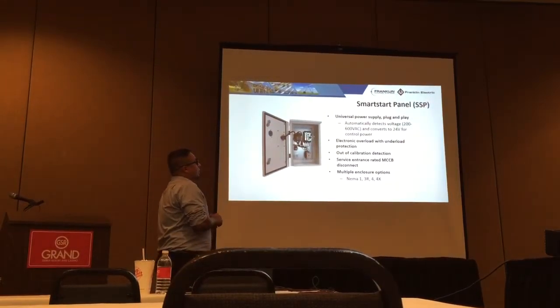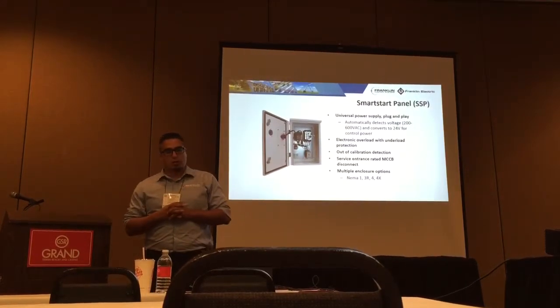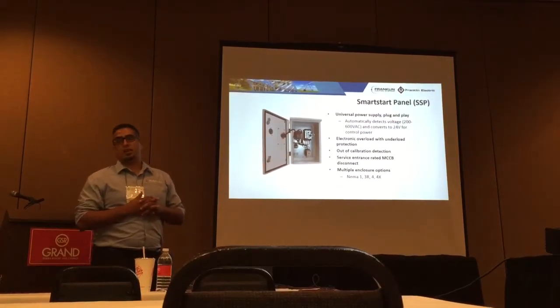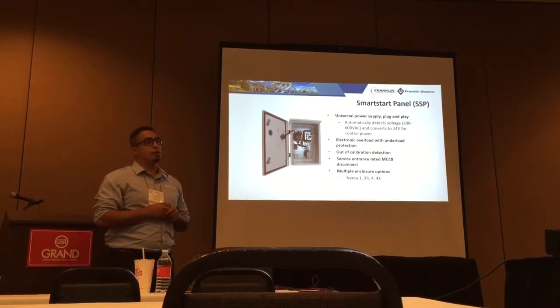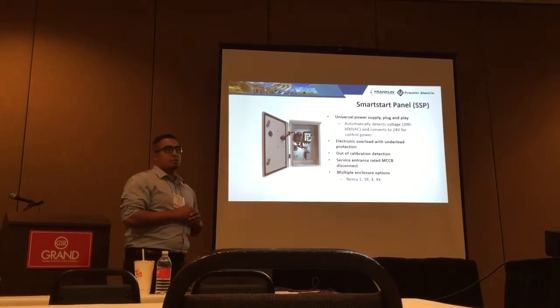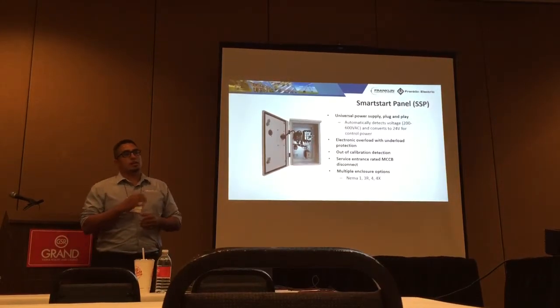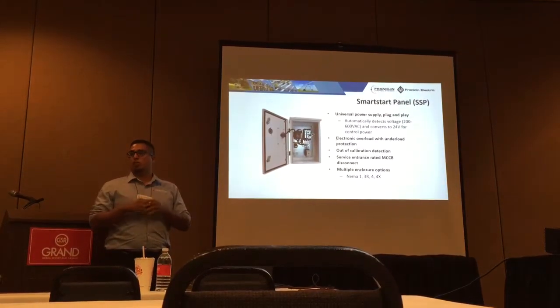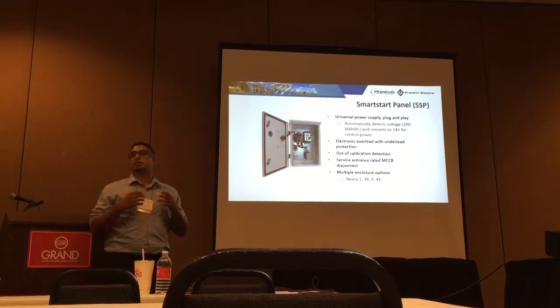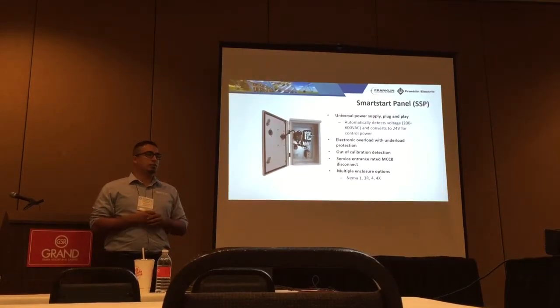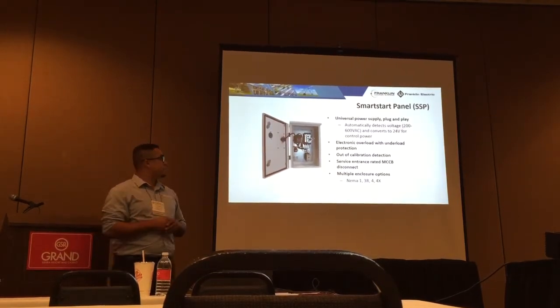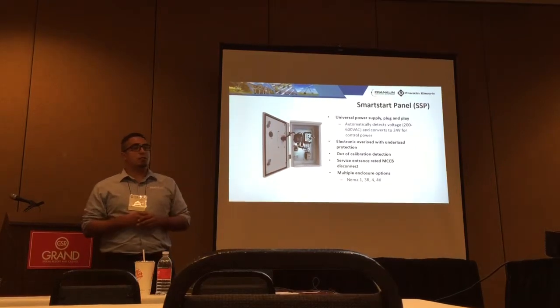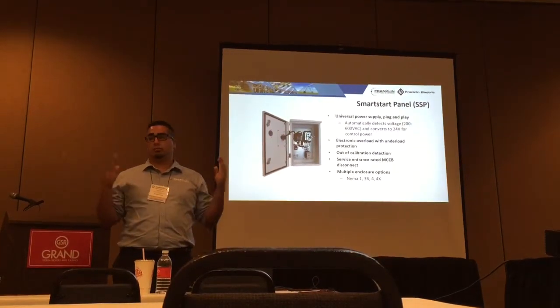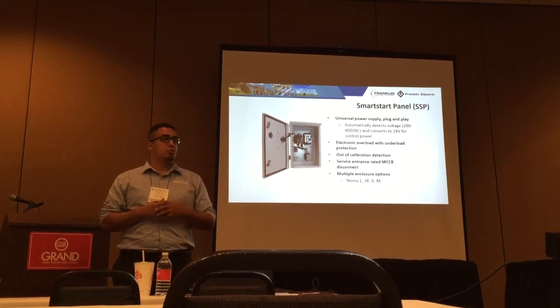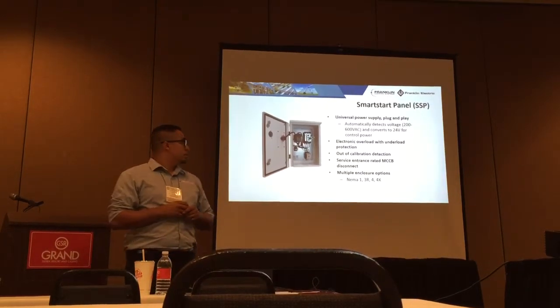Okay. The other big thing that the Smart Start panel has, and we're also going this way with some of the other panels, specifically the new sub monitor we're working on, is automatic voltage detection. So that's another thing for motor protection, specifically more for motor control protection, is there's no more need to change the coil voltage on that contactor. Okay, and even for stocking purposes, we limit it down to maybe 4 or 5 sizes for a very, very wide amperage range because you're carrying one coil voltage.